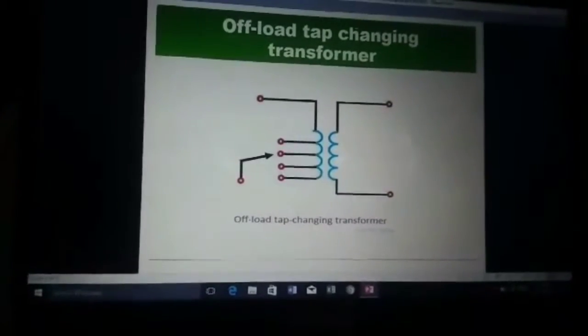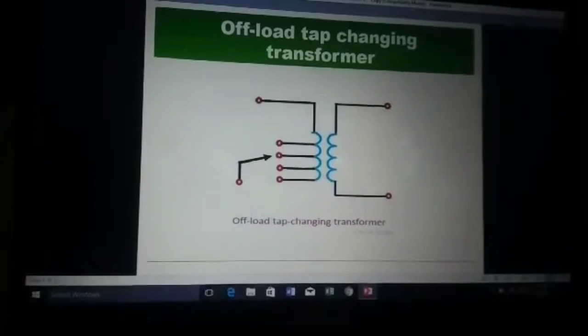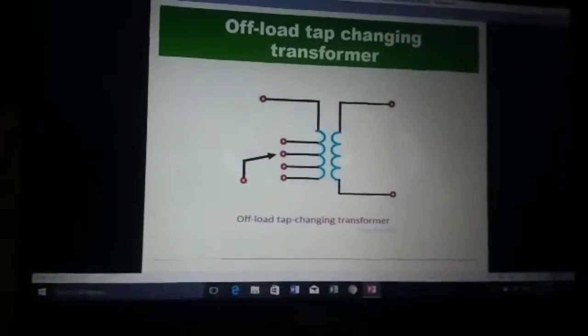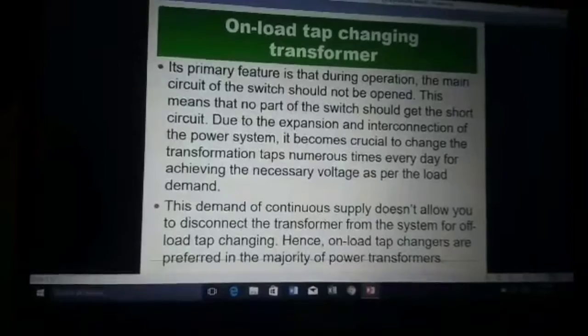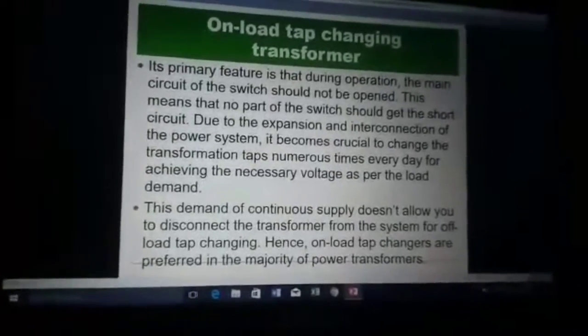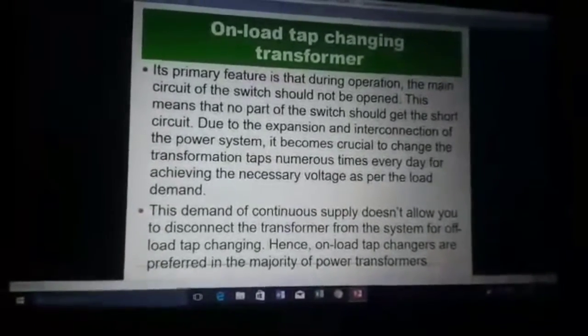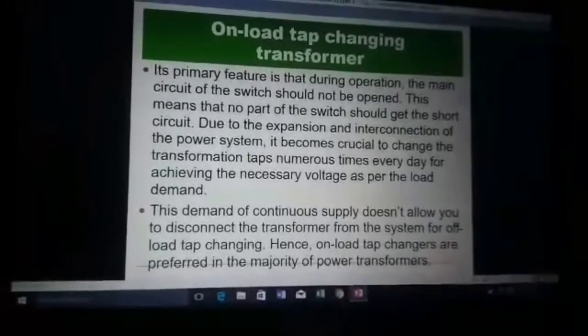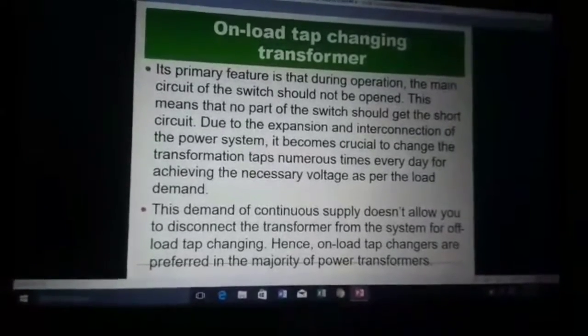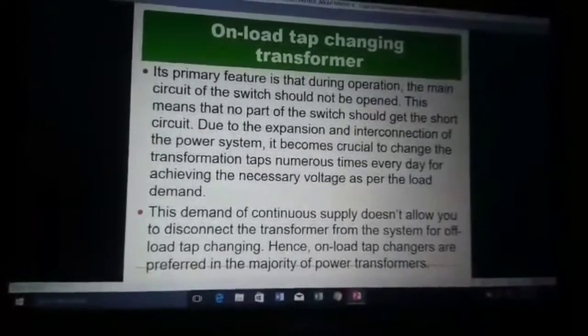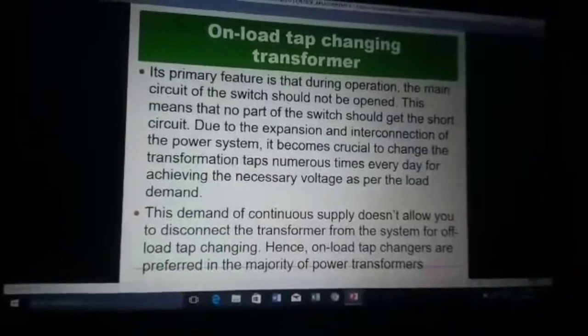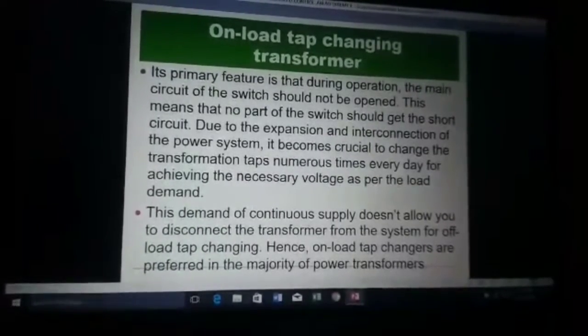So here's the image of an offload tap changing transformer. On the other hand, on load tap changing transformer, its primary feature is that during operation, the main circuit of the switch should not be opened. This means that no part of this switch should get the short circuit.